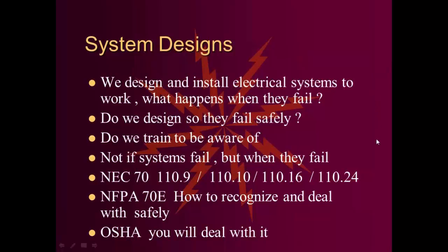The National Electrical Code, NFPA 70, in 110.9 talks about interrupt rating. 110.10 talks about withstand rating of equipment and breakers. Do we know what that is? It's stamped on every breaker. It's in the product safety or product standards. It's on every label on the inside of a disconnect or a panel. We never look at it.